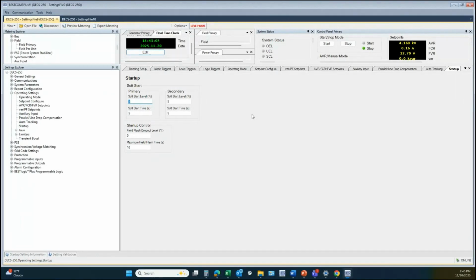Startup. The soft start settings within the DECS allow you to start up excitation and eliminate the overshoot on startup. Analog AVRs will try to go full on when you first start bringing the generator up. Oftentimes, depending upon how fast your machine comes up, your generator voltage can come up and actually exceed your nominal voltage. To help prevent that, we have the soft start settings within the DECS, which slows down that process so it ramps up excitation to bring up your generator voltage more slowly in order to prevent the overshoot.